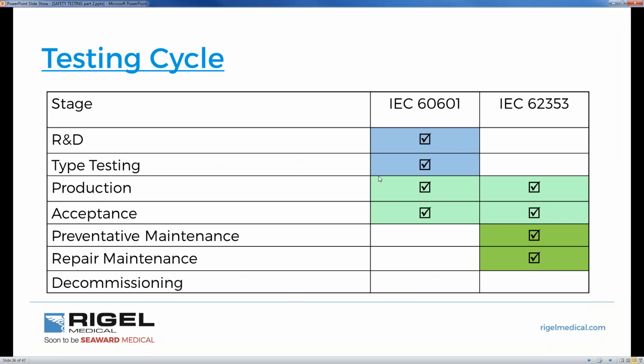I'll just reiterate that again. 60601: R&D, type testing, production working environments, acceptance testing. There is crossover here. You can use 62353 for end-of-line production and for acceptance testing, but more importantly, the standard is designed for our preventative maintenance and repair maintenance of a medical device. Very clear. I must reiterate those points.